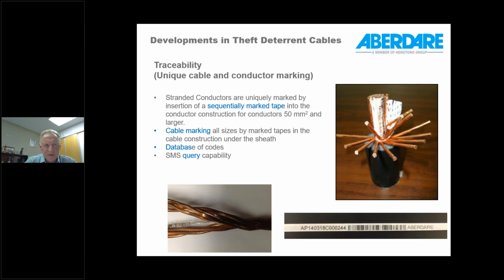So traceability, I would say, is the one area where, in essence, the whole industry has implemented this kind of marking, particularly on medium voltage and some of the bigger sizes of low voltage cables. It provides unique traceability for the cable and for the conductor, depending on the size of the conductors. Here you can see examples of a tape which has been introduced into a conductor. This is just a bare conductor. It shows the barcode, the manufacturer's name, and then also a number. So typically this is the tape that's used.